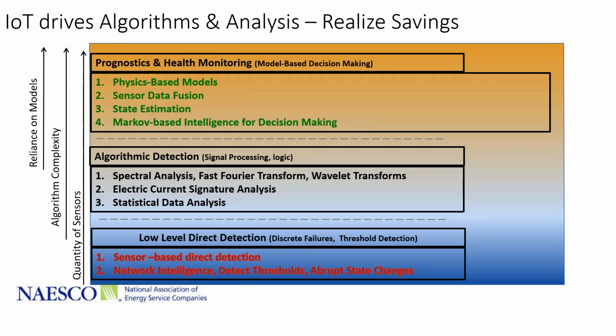The way to view this slide is look from bottom up. You can have discrete failures detected through threshold-based detection—a dirty air filter could be a simple example, sensor-based direct detection. As you go up layers, you have algorithmic detection, which requires taking sensor information. For example, you could put a vibration sensor on an HVAC unit and tell a lot about what's happening with the compressor, but it requires taking that vibration information, doing Fourier analysis, or using a power sensor to do current signature analysis, understanding normal behavior, and teaching the algorithms what's normal so they can pick out abnormal behavior as it happens, for condition-based maintenance and things like that.